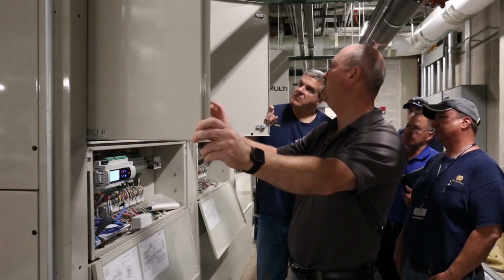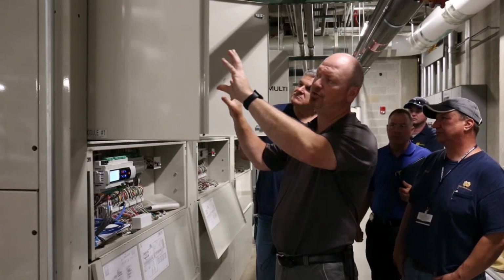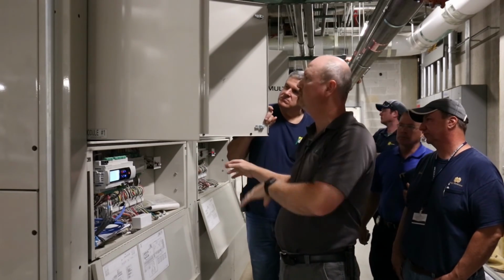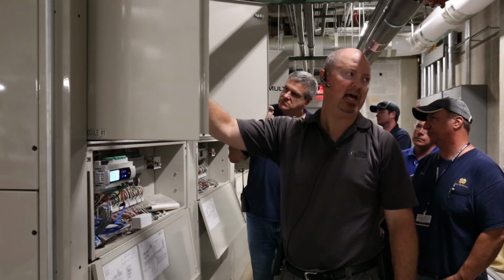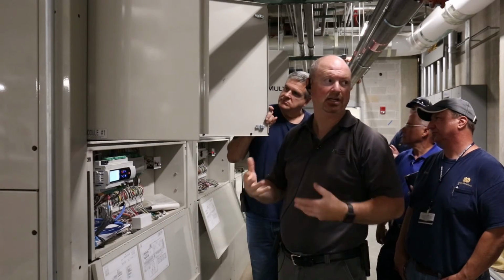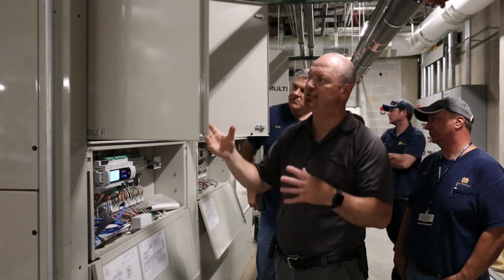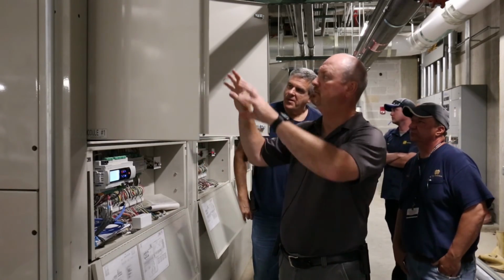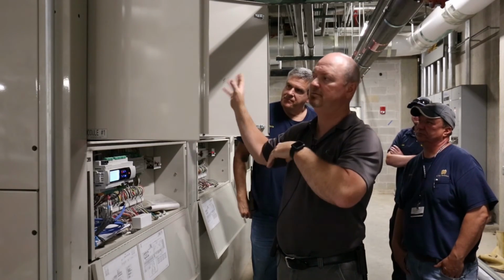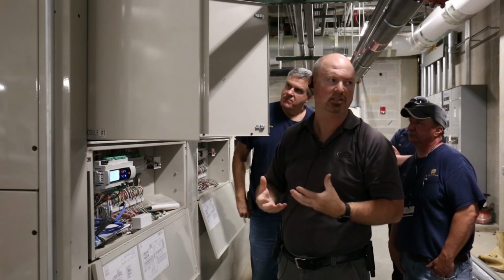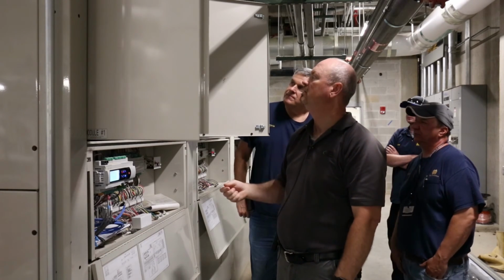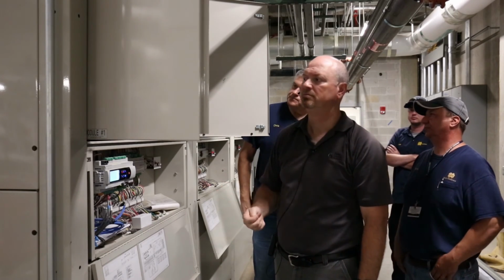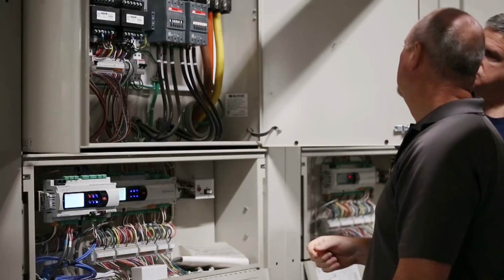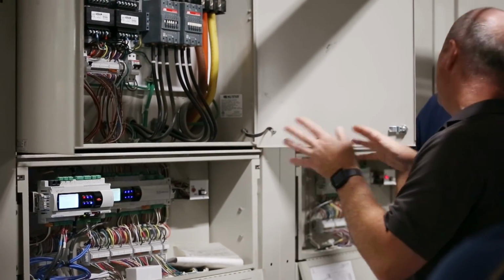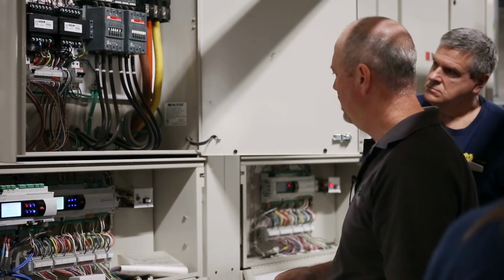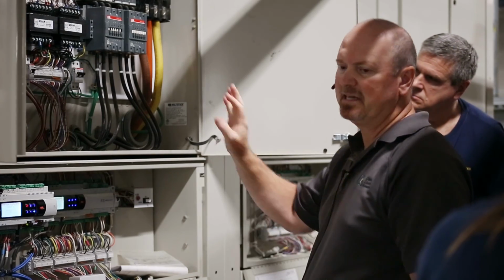Yes, you've got one on each circuit. You've got 2 circuits per module, and it'll stage that to keep you out of your low pressure conditions. Instead of running 2 on one circuit, you can spread it out a little bit, and it actually runs more efficiently that way, and it stays out of the danger zone. And each module has the exact same setup going down through here.